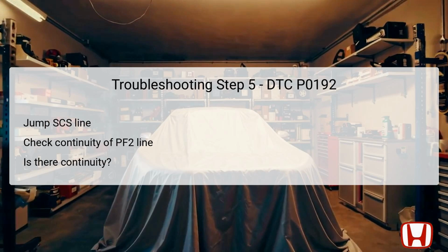The fifth troubleshooting step involves checking for potential short circuits in the PF2 wire leading to the fuel rail pressure sensor. Begin by ensuring the ignition switch is set to lock 0 and once again executing the SCS line jump with the HDS. Disconnect the PCM connector A49P to isolate the circuit. Measure continuity between the indicated test points under the specified conditions. This involves checking from the PF2 connector to body ground.